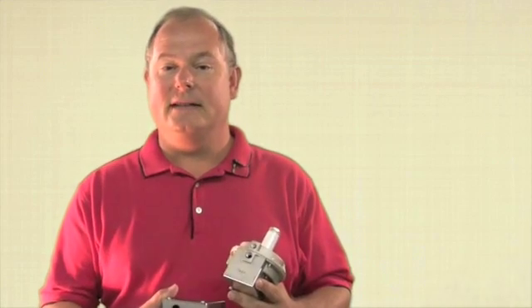Three ways we can hook up an airflow switch. If you have plenty of pressure, we just take one sensing line from a pressure port, put it in line right ahead of the fan, and we can prove through this switch that fan is making pressure.